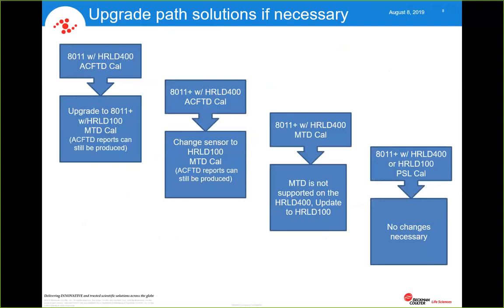If you have an 8011 plus, this is the next one in transition. If you have an 8011 plus with an HR LD400 sensor utilizing the ACFTD calibration, then simply you have to just change the sensor to an HR LD100 sensor, have it calibrated with medium test dust, and then again we can report out to the old legacy standards with that configuration.